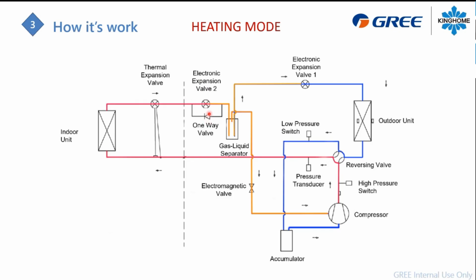Because in cooling mode this one was a check valve, it will be blocked. So the refrigerant cannot flow in that direction. You will need to pass through that EEV. This one will just manage the system to make sure you have 100% liquid. So the liquid line is 100%. So you will fill up this gas liquid separator again, take 100% liquid from this separator, and then go to your EEV number 1. This one now will act as your metering device. On the other half of this valve, you will have low pressure, low temperature, and then you can go to the outdoor coil to absorb heat from the outside temperature, and then go back to the compressor.